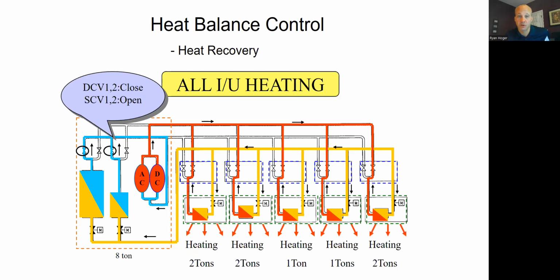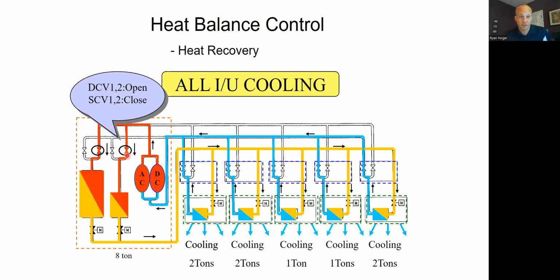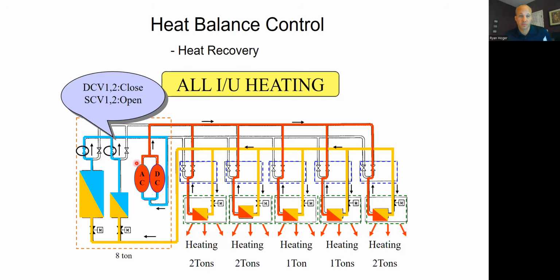When I switch to heat mode, all heating, in this case everybody wants heating. Okay, great. It works exactly the same, except for my valves. See these 2 valves? These guys are open. These guys are closed. When I go to heating mode, these guys open, these guys close. It's just another way of doing the reversing valves, a little different than those small residential systems you looked at, but same idea. Now hot gas leaves the compressor and does not go to the coil outside to get rejected. Instead, the hot gas goes to the indoor units to send its heat to the inside, thereby sending me cooler refrigerant back where I can pick up heat from the outdoors. It works just like every other heat pump that we've talked about in the past.